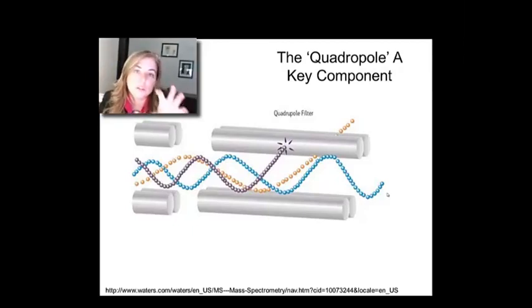And at a particular tuning of the quadrupole, a particular magnetic field strength, one ion will make it all the way through. It will have an extremely straight path down the quadrupole. But if the ion's charge to mass ratio is just a little bit different, it's actually going to deflect and it's going to end up leaving the quadrupole.